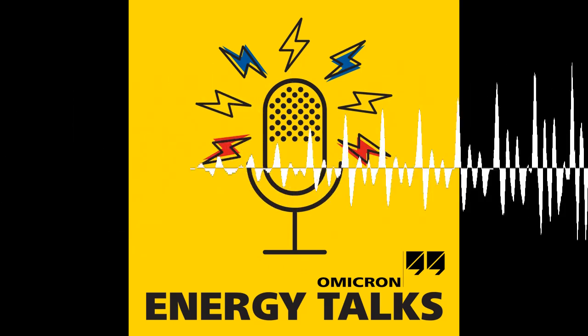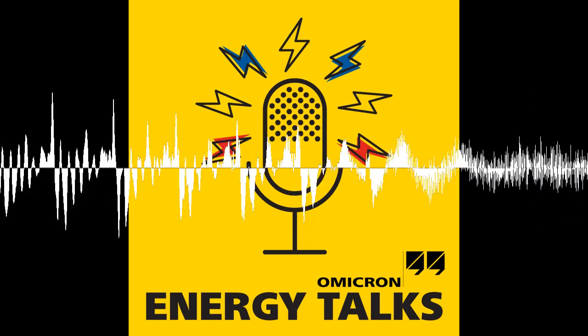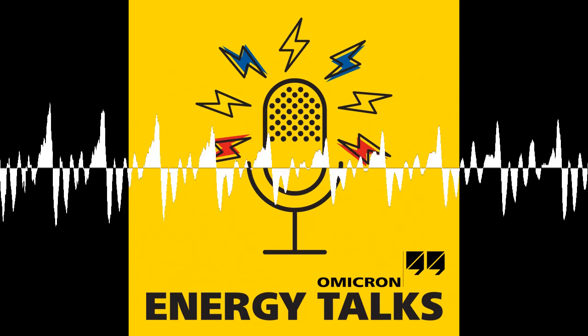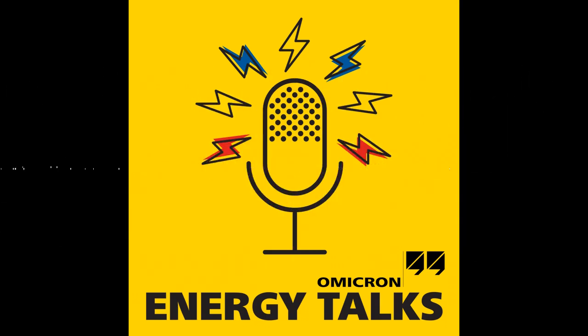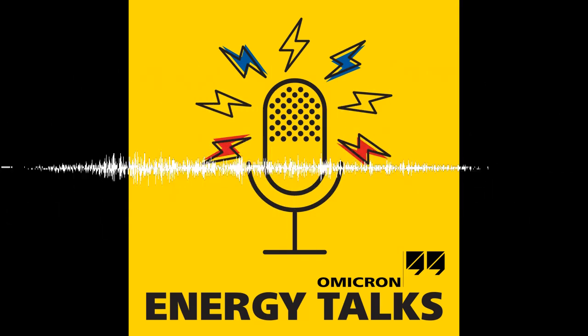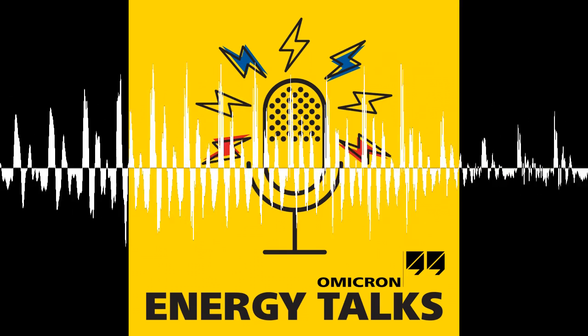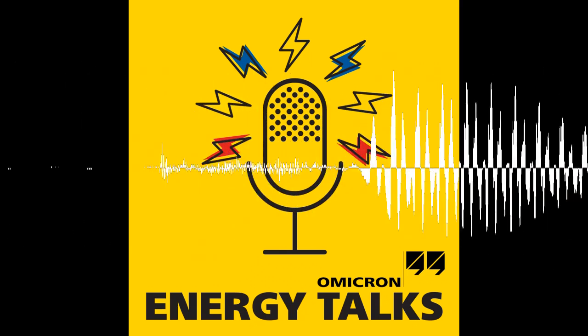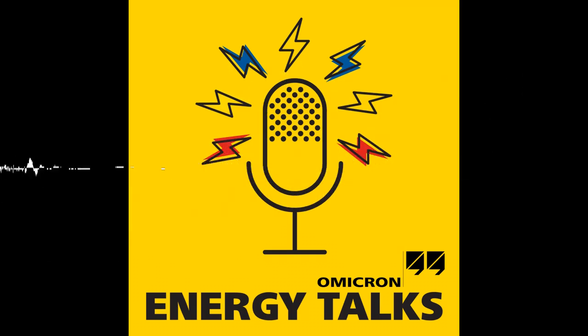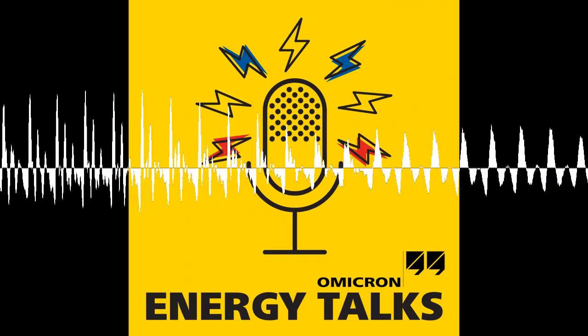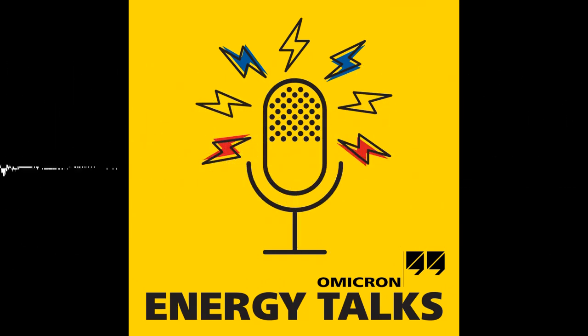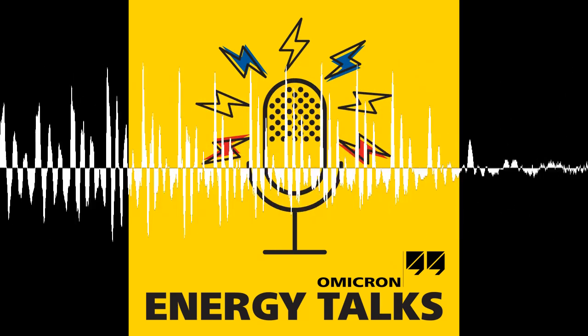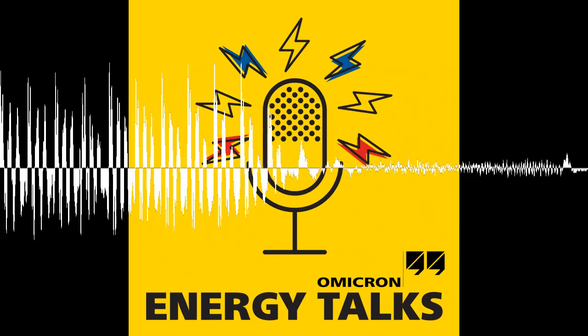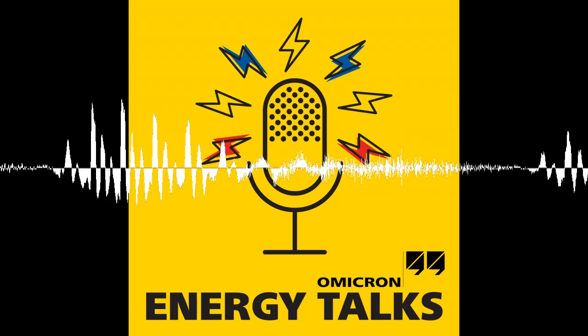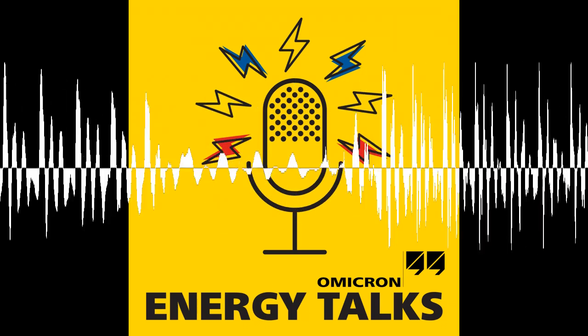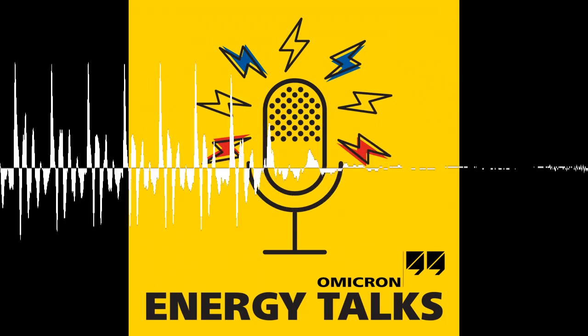Andreas, could you describe what switchgear is and what function it has in power substations, especially for our listeners who are not quite familiar with switchgear? Yes. Switchgear, as the term implies, you are switching stuff, but different kinds of devices switching. So we have the most important one, I would say, the circuit breaker as a switching device, which breaks the circuit, separates the circuit when there's a fault on the line. But we have also disconnectors. They're also separating, but they're not capable of carrying any short circuit current. And we have grounding switches. They're also switching, but their purpose is only to ground the equipment to work there. So they're all switching, but with different purposes in the grid.